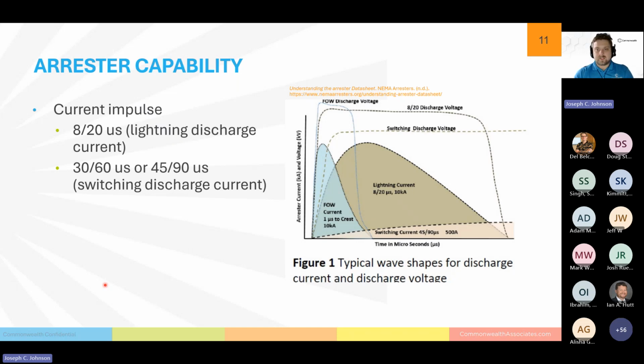So you can see in this diagram here, there's several different waves. You have your front of wave, very steep, your voltage discharge up here about as steep as it gets at the highest peak, and you see different voltage and current discharge values depending on the wave type. You can see the lightning is a significantly faster rise and then falls off, whereas the switch hasn't even really begun to hit its peak by the time lightning's fallen off. A lot more energy is actually underneath the switching wave usually.